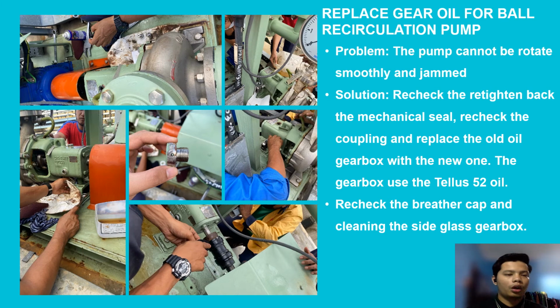So the other activity that we did is replacing gear oil for the ball recirculation pump. The pump cannot be rotated smoothly and is jammed because we haven't used it for a long time. We need to change the old oil with new oil and check the mechanical seal. The old oil will be flushed out and replaced with the new one. The breather and the side glass of the gearbox also need to be cleaned of any debris.